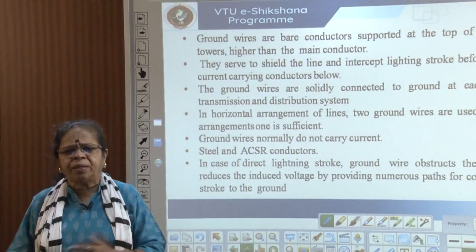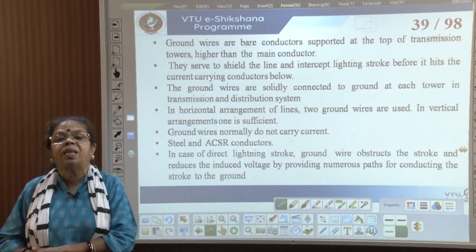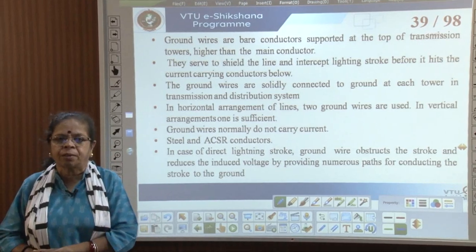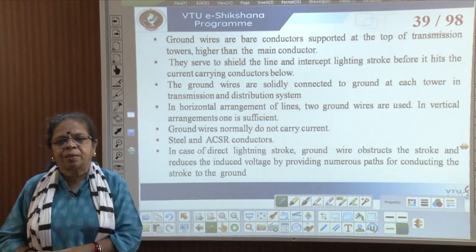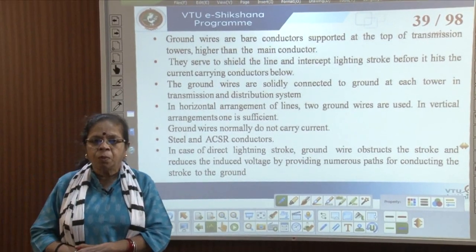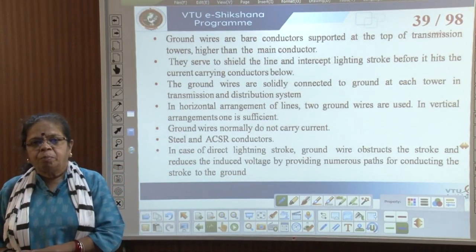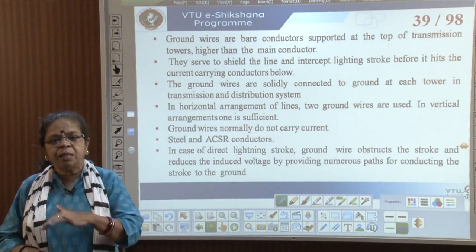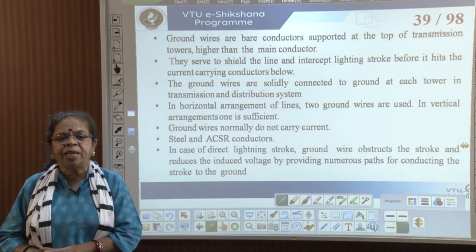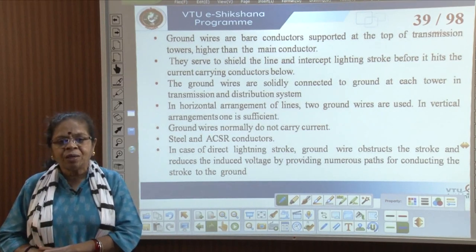Ground wires are bare conductors supported at the top of transmission towers, higher than the main conductor, so that lightning strikes the ground wire before striking the transmission lines. They serve to shield the line and intercept the lightning stroke before it hits the current-carrying conductors below. These ground wires are solidly grounded at each tower, both in the transmission system and in the distribution system.